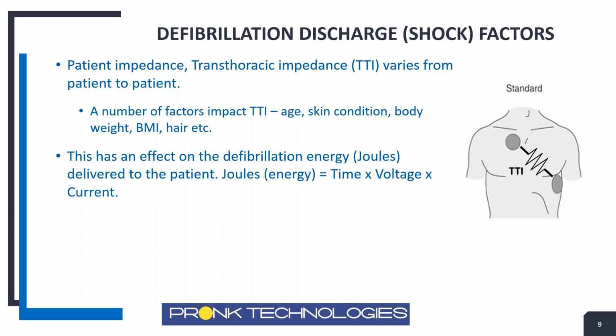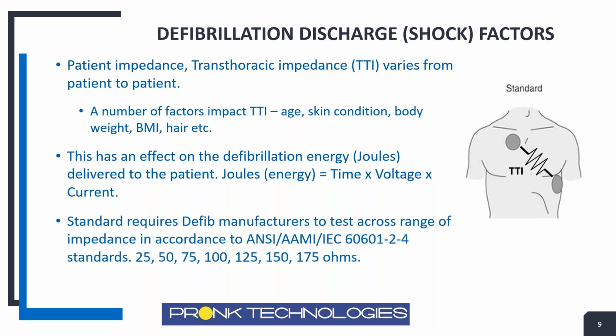Of course, the defibrillator is delivering the energy in joules. The general basic formula is: how much energy is being delivered over what time, multiplied by the voltage, multiplied by the current being applied. The voltage is calculated by the resistance or impedance of the person times the current being discharged. So depending on that person's impedance, the voltage will vary, which varies the energy delivered to the patient. It's important to understand that principle because it could impact the defibrillator's performance, and so we need to be aware of that.